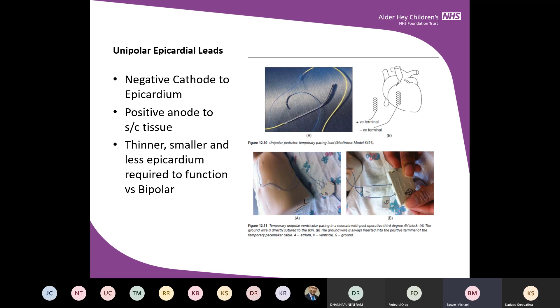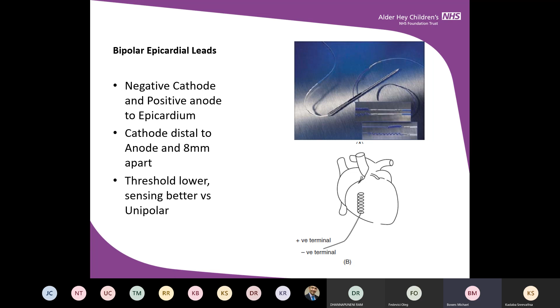Bipolar leads have positive and negative terminals placed on the epicardium, usually 8 to 10 millimeters apart, to allow the bipolar circuit to be present and effective. And again, optimization of these is useful because the higher the thresholds, the less time the leads are likely to last, and the more damage you cause to the tissue underneath due to high output voltages.